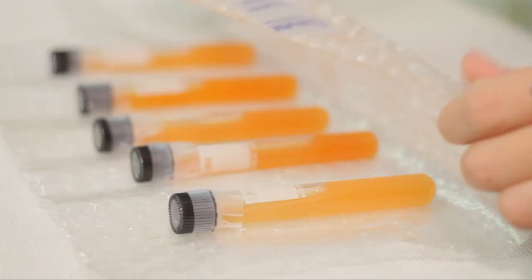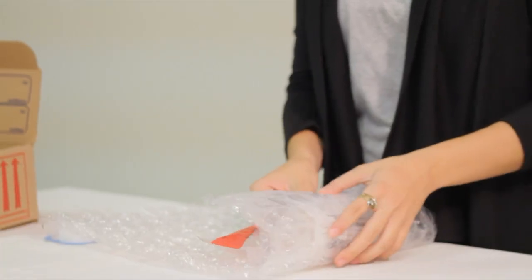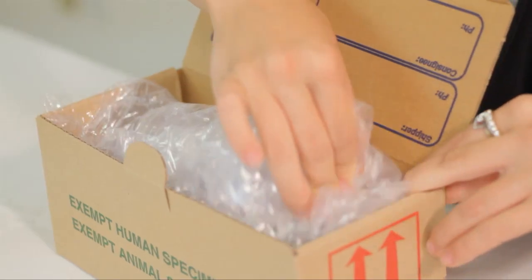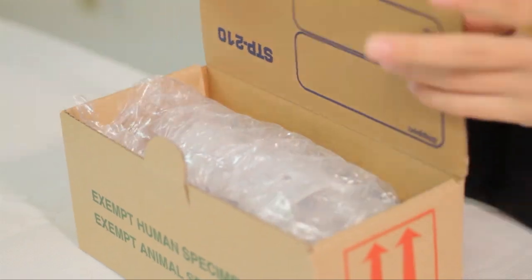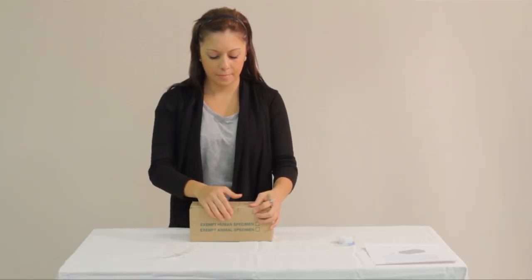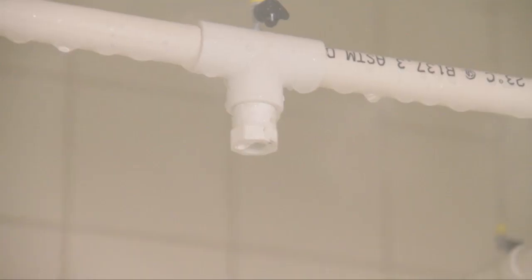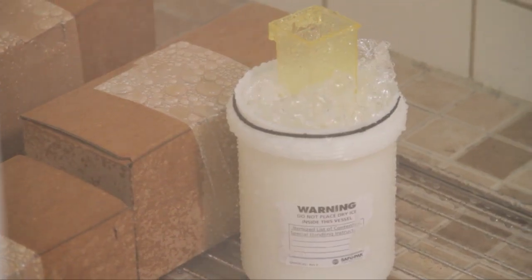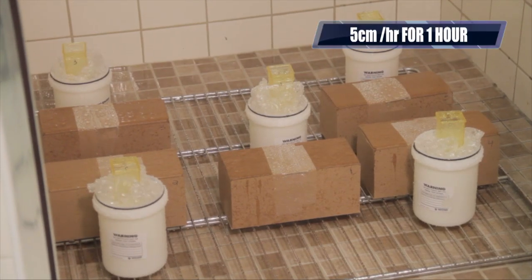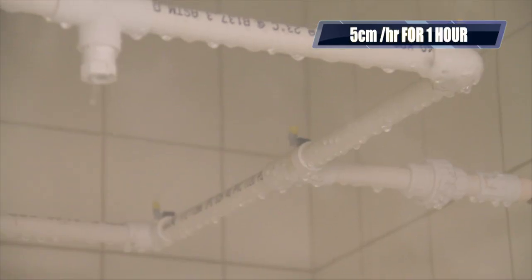Package testing must always be performed on a completed package assembled according to the manufacturer's package design. Before performing a package test, the package must be conditioned. The complete package must be subject to a water spray of 5 cm per hour for one hour.